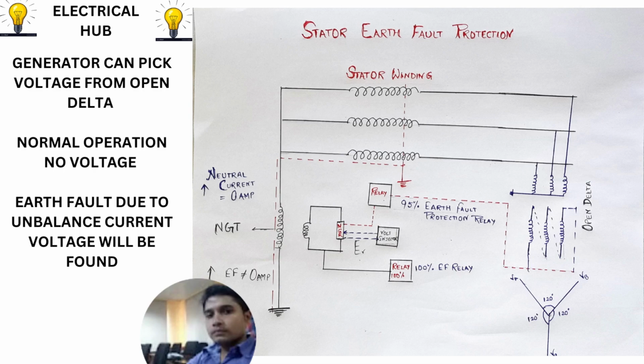So what happens in the open delta connection? During normal operation, there is a balanced current flowing which, due to the 120-degree displacement, adds up to zero. But if one of the windings is grounded, then there will be an unbalance in the current. Due to the unbalanced current, there will be a voltage drop, and that voltage drop will go into the relay, and since it is a voltage sensitive relay, it will trip the alternator.